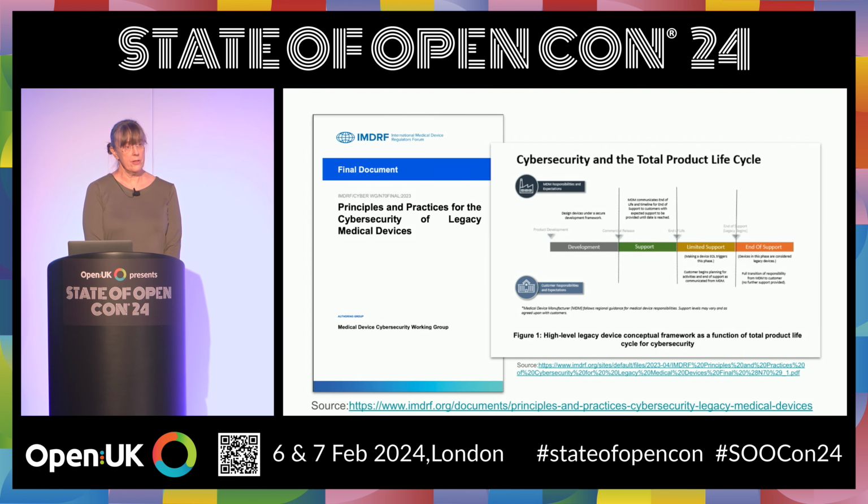And so the International Medical Device Regulators Forum basically got together last year and put together a principle and practices of cybersecurity of legacy medical devices to start to guide people towards this area. And one of the things that was really showing up in there is the whole concept of the total life cycle of a product and how to basically look at support. Is it in support? Is it out of life? End of support, end of life? How do you consider it at this point in time? So getting to that stage of what's in support, what's not in support, is starting to show up.